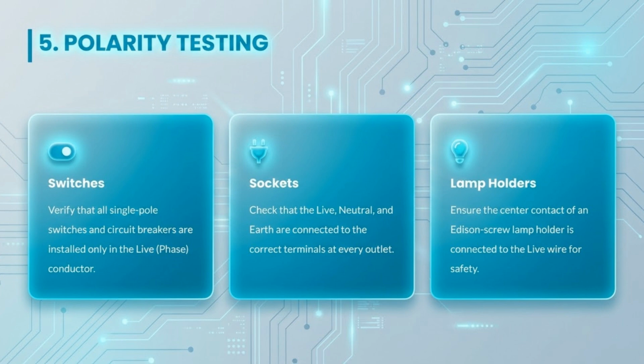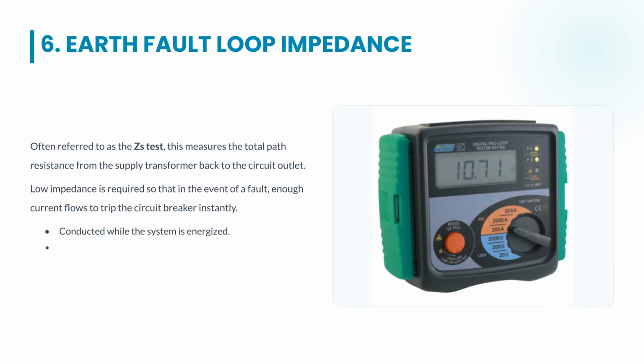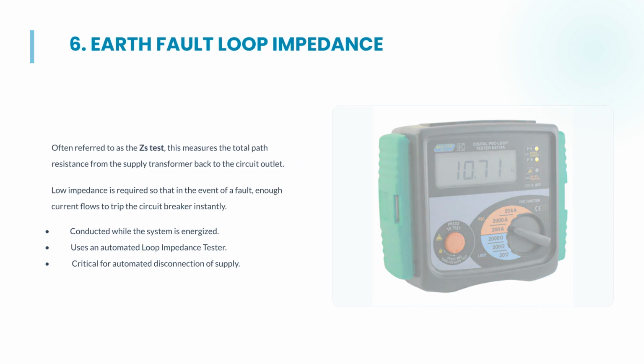Polarity testing ensures correct wiring orientation for switches, sockets, and lamp holders. For safety, single-pole switches must be installed only on the live conductor, and the live, neutral, and earth connections must be correct at every terminal. Earth fault loop impedance, or Zs testing, measures the total path resistance from the supply transformer to the outlet. Low impedance is required so that enough current flows during a fault to instantly trip the circuit breaker.